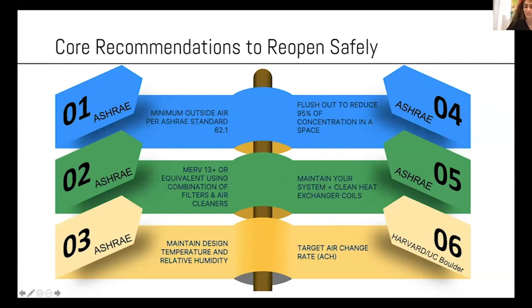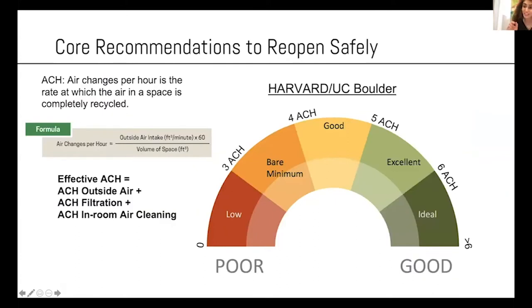What is air exchange rate? Air exchange rate, as the name indicates, is how many times you're changing the air in your building per hour. So if you have an air exchange rate of 6, you're changing the air in your building 6 times. It's a very easy equation, especially when it comes to outside air. You take the outside air flow volume in cubic meters per hour and divide by the volume of your space in cubic meters, and you obtain 1 per hour.